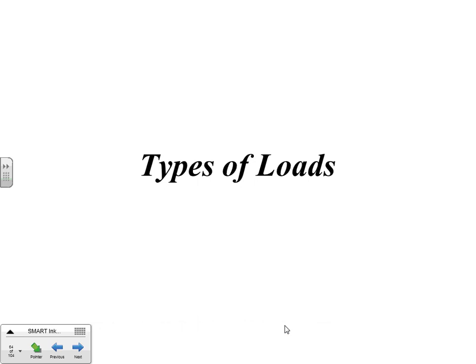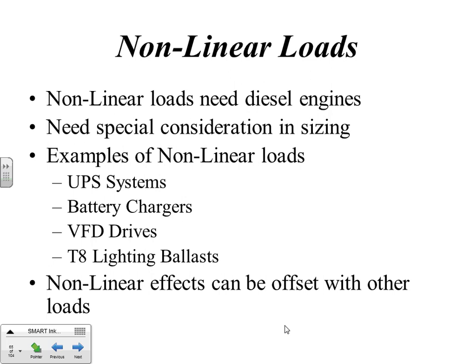Let's talk a little bit about different types of loads that you're going to see, especially in the nonlinear category. Nonlinear loads need diesel engines. I say this, it was only a personal preference. It's not a requirement. But if you have a heavily nonlinear load, it's best to have a diesel. And that's only because of how a diesel engine reacts to a load as opposed to a gas. Some of the nonlinears are very fussy. UPS systems especially look at the input, and if it sees any fluctuation, it goes to a bypass mode. Diesel engines are a lot stiffer in their reaction to that load. We don't have issues there. They also need special consideration and sizing because we've got higher than normal neutral currents flowing.